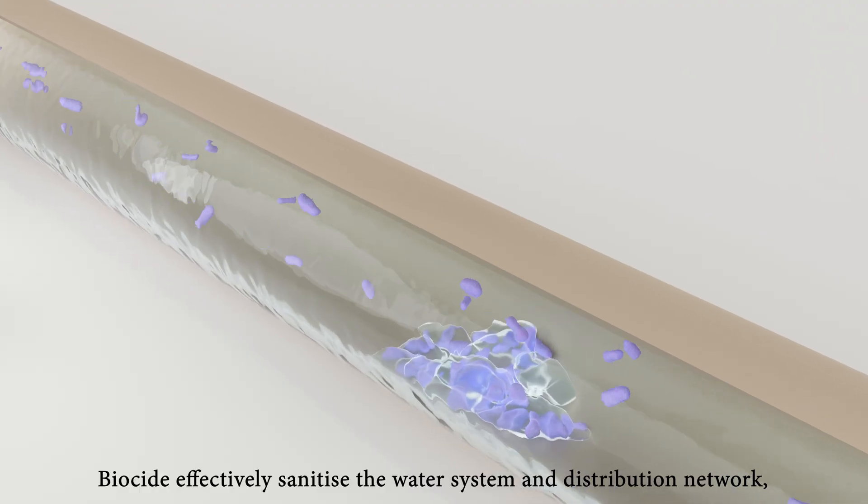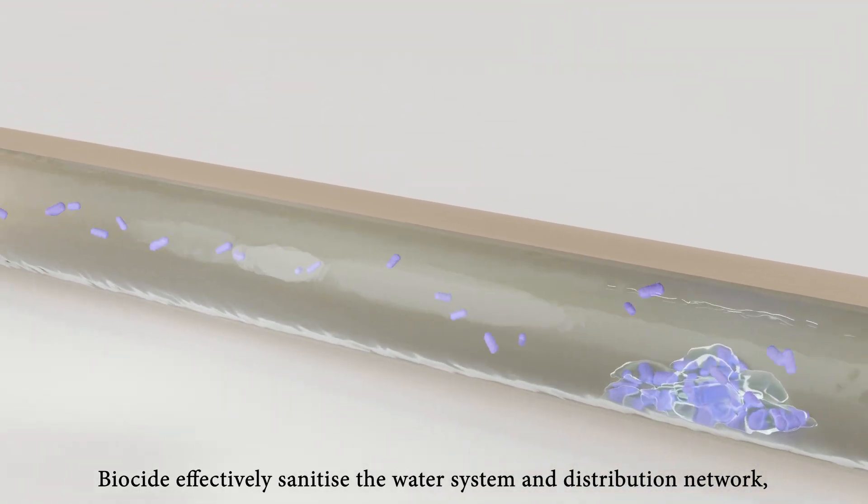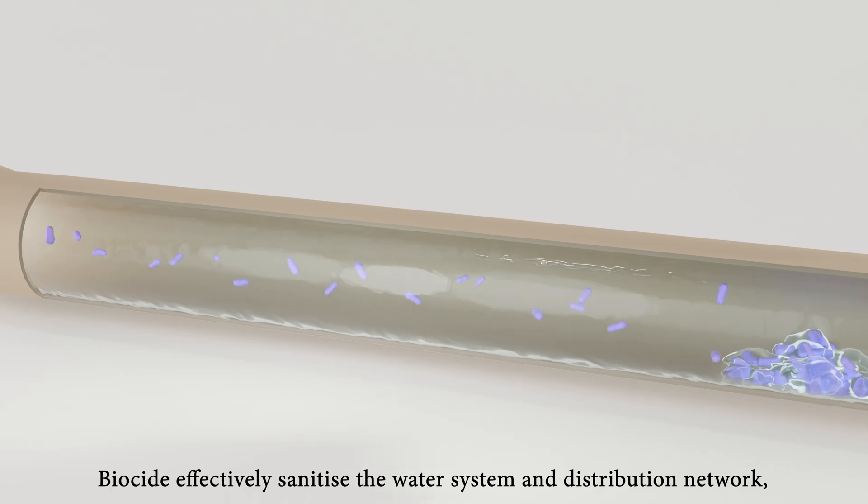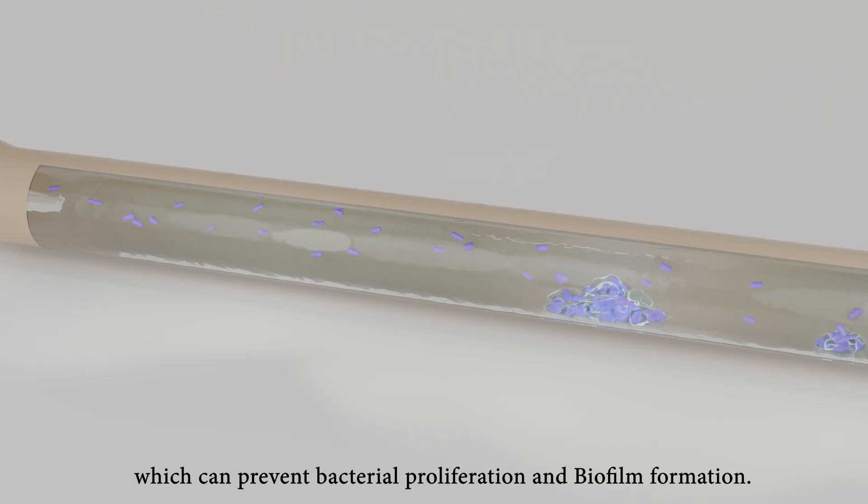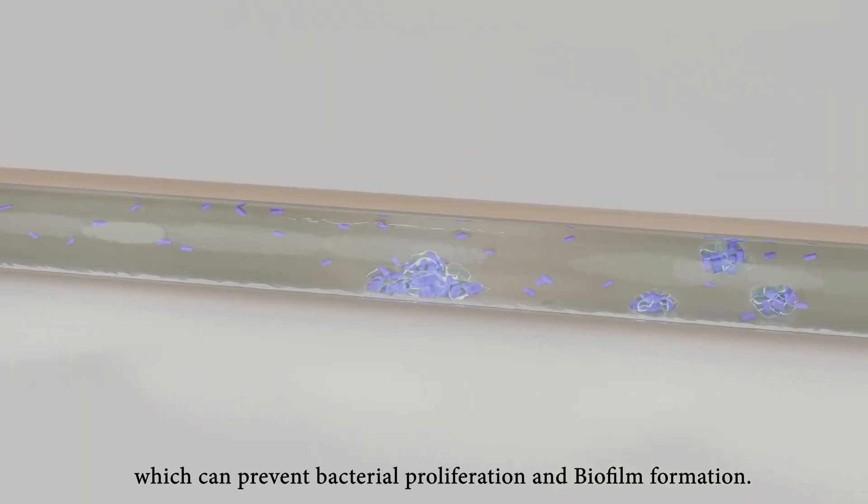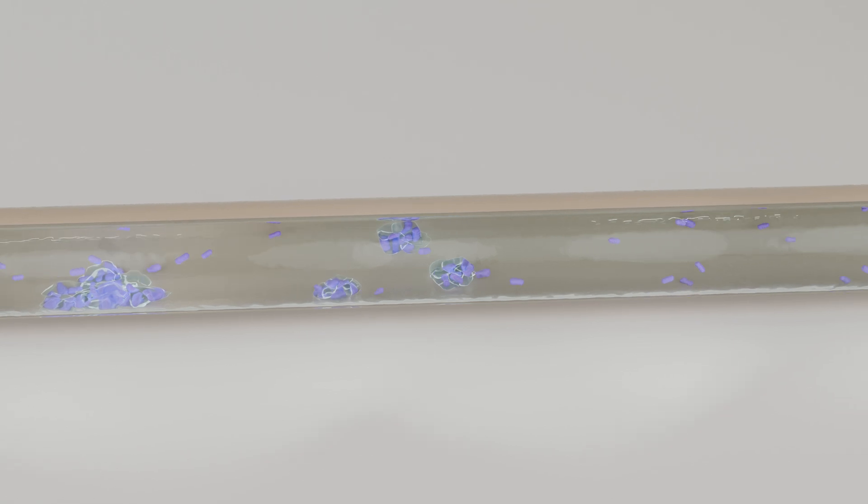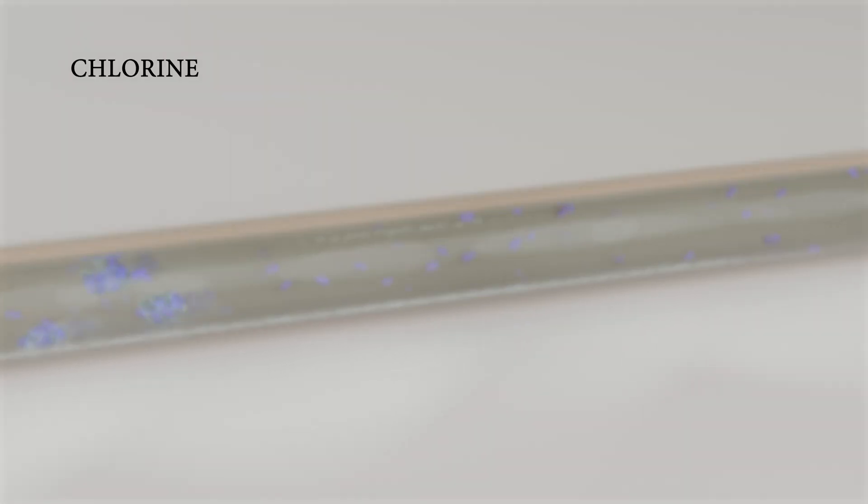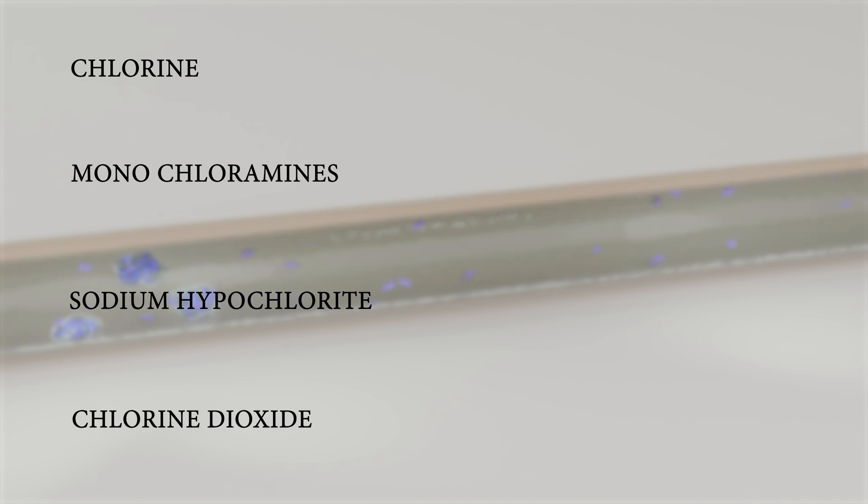Highly concentrated biocide is essential to effectively sanitize the entire water system and distribution network, which can prevent bacterial proliferation and biofilm formation. The most common chemical biocides are chlorine, monochloramines, sodium hypochlorite, and chlorine dioxide. Other biocides include peracetic acid and hydrogen peroxide.